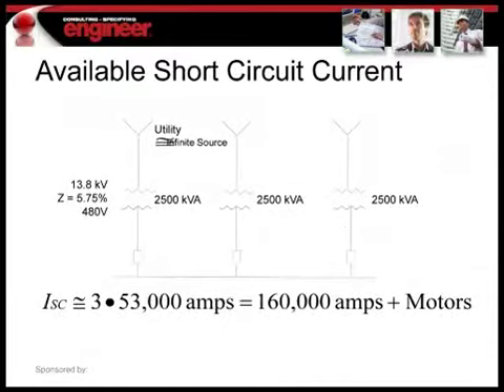And then this is a configuration that you might find in a relatively large hospital environment. These transformers are arranged in a secondary spot network arrangement, and you can see that the available short circuit current jumps up considerably. It's 3 times that which is available from a single transformer. This is also the arrangement that you might find from an urban utility. For example, here in Seattle, Seattle City Light uses secondary spot network service configurations to serve many of their buildings in downtown Seattle. So you might be deriving your power from one of these utility types, in which case the available fault current at the 480 volt level is quite large. We'll talk a little about what that means with respect to your transfer switch design.